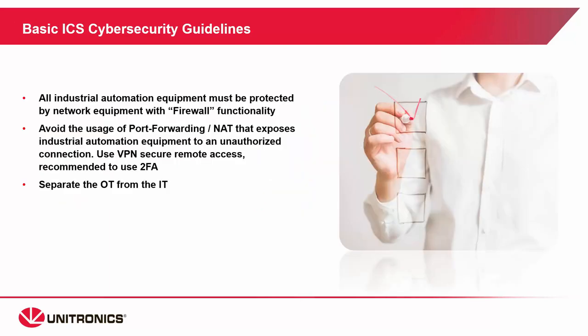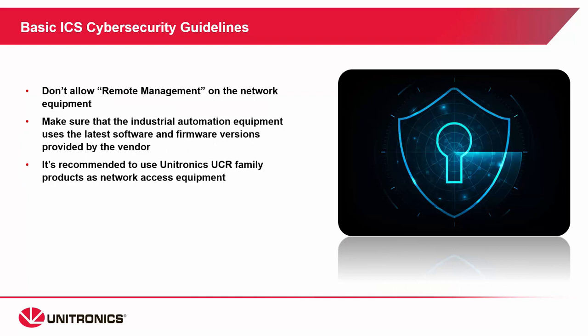Here are some general ICS cybersecurity guidelines. All industrial equipment should be protected by network equipment with firewall functionality. Avoid port forwarding or network address translation. Instead, use VPN, ideally with two-factor authentication. When possible, separate OT — operational technology — from IT, information technology. Don't allow remote management of any network equipment, like routers.